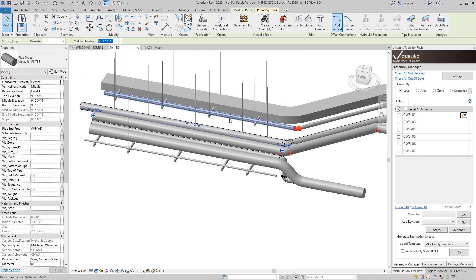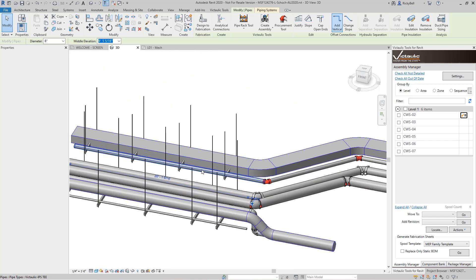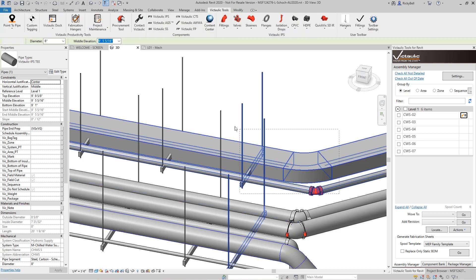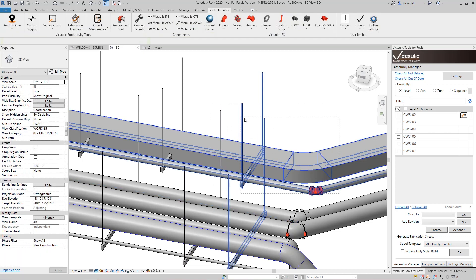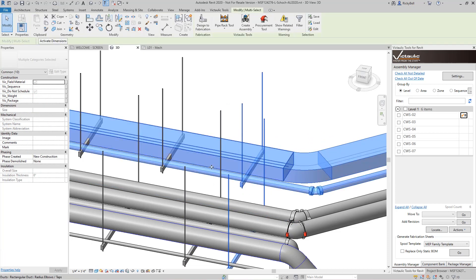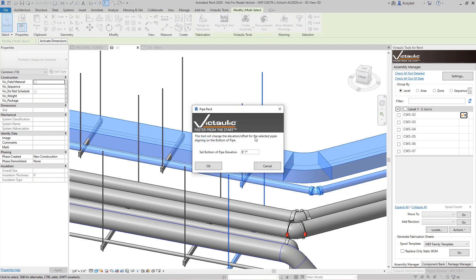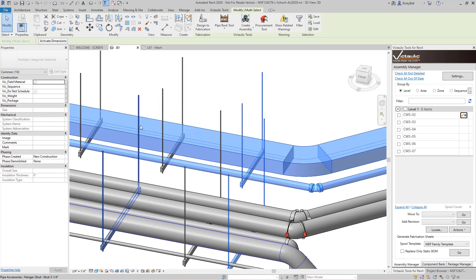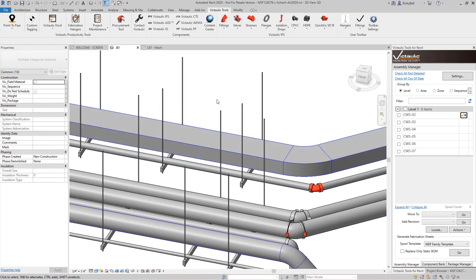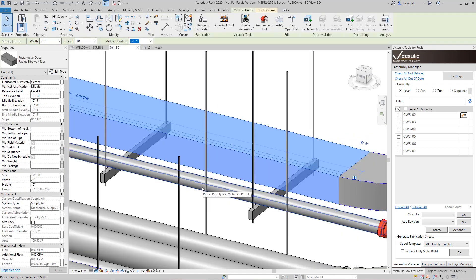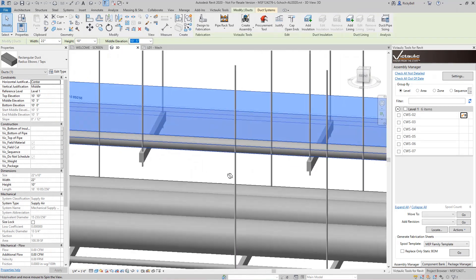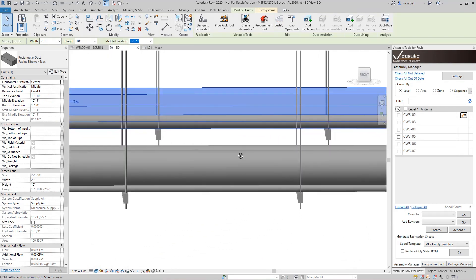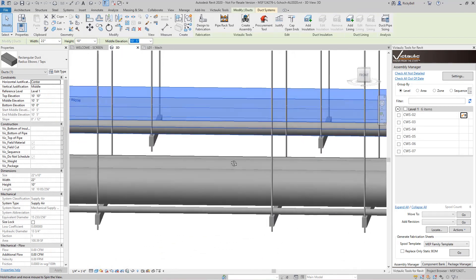I have another rack up here with a similar situation. It's a rectangle duct along with another piece of pipe. So I'll go ahead and highlight them. You could even put some fittings into your selection. It really doesn't matter. If it can change the elevation, it will. So back to the pipe rack tool. It's telling me nine foot seven is the lowest it could find. This particular hanger is hung at ten feet. So I'll hit ten feet right there and click OK. And now everything's adjusted to be resting on that ten foot hanger. And right beneath it is the nine foot rack that we created.